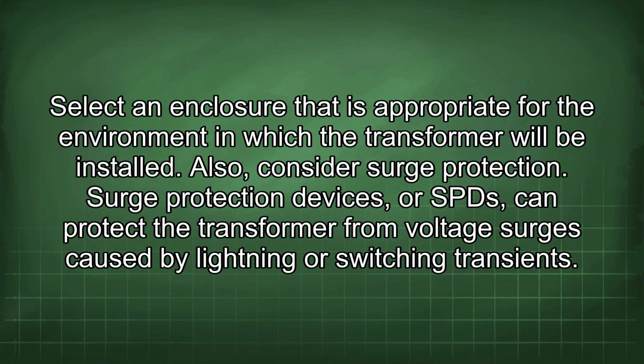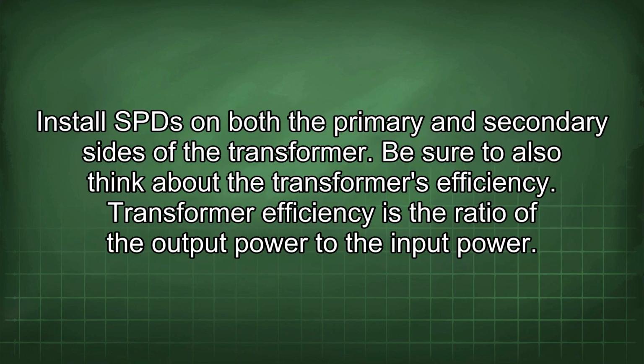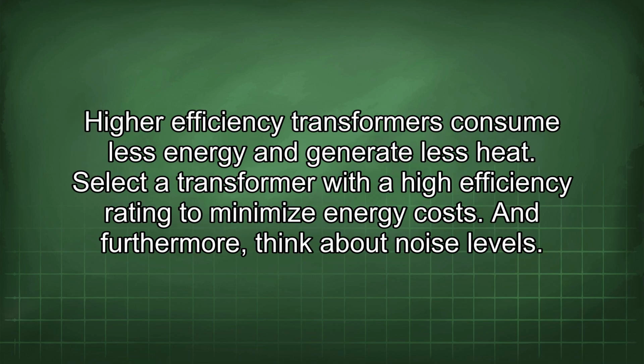Also, consider surge protection. Surge protection devices, or SPDs, can protect the transformer from voltage surges caused by lightning or switching transients. Install SPD on both the primary and secondary sides of the transformer. Be sure to also think about the transformer's efficiency. Transformer efficiency is the ratio of the output power to the input power. Higher efficiency transformers consume less energy and generate less heat. Select a transformer with a high efficiency rating to minimize energy costs.